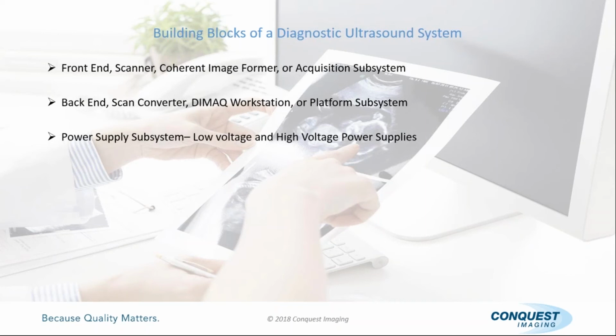Then you have your high voltage. A lot of people say, well high voltage for your printer, that's 115 volts, and that truly is high voltage I guess. But when we're talking high voltage in ultrasound, we're talking about the voltage used to excite the crystals in the probe. That's the high voltage that causes the probe crystals to send out sound waves.